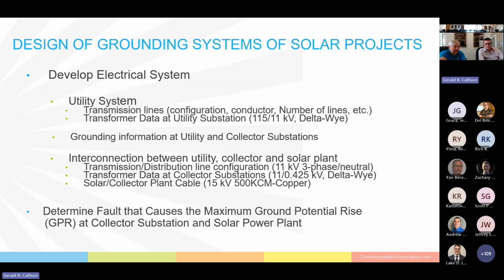The same thing happens when you put grounding systems together. So in order to come up with a good design, you need to know a lot of information, and you don't necessarily have all the information in one spot. The model that we're going to discuss shows how the different ground grids interact. I'm going to describe it on this slide, which is the utility system. We have transmission lines coming in, and you want to know the configuration: what the conductors are, how many lines there are, what the shield wires are made out of, and what the pole grounds are. There's a lot of detailed information you want to find out.